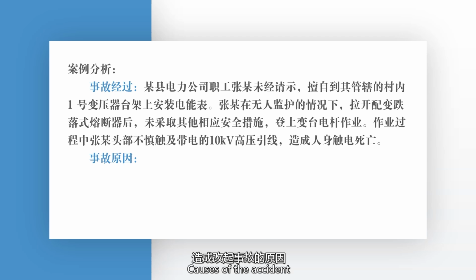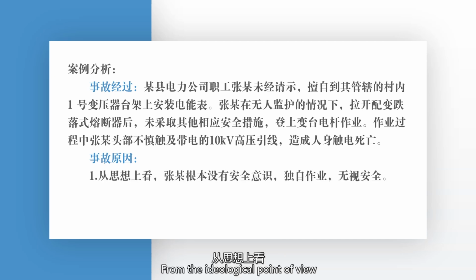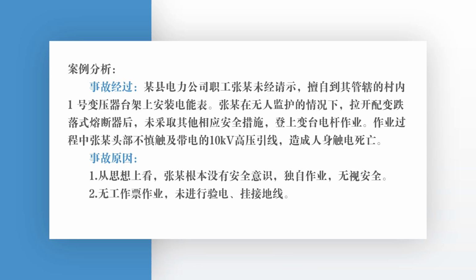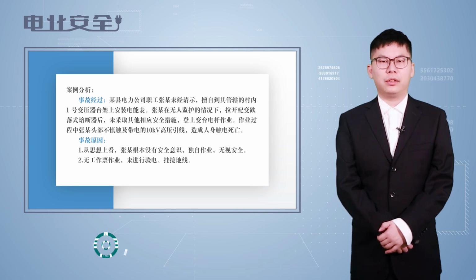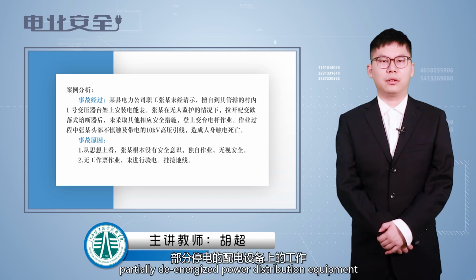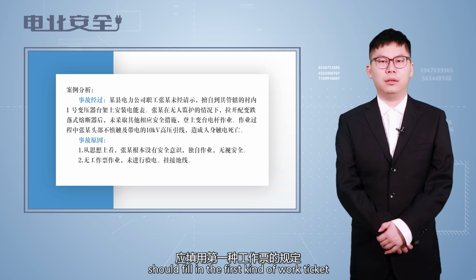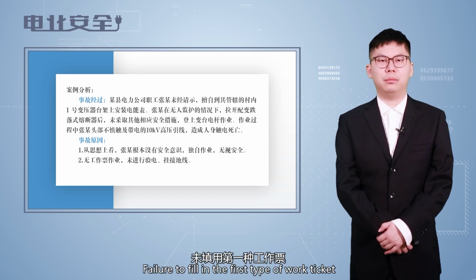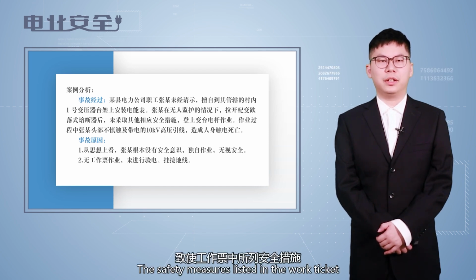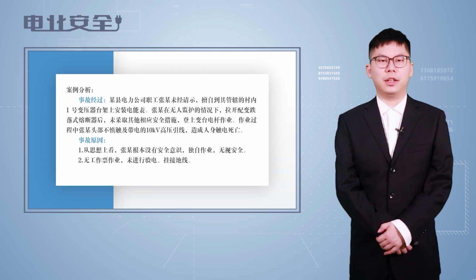After investigation, there are 3 main aspects to the causes of the accident. From the ideological point of view, Zhang simply did not have safety awareness, working alone, disregarding safety, operating without a work ticket. Zhang violated the safety regulations: work on fully or partially de-energized power distribution equipment should fill in the first kind of work ticket. Failure to fill in the first type of work ticket. The safety measures listed in the work ticket cannot be strictly implemented.